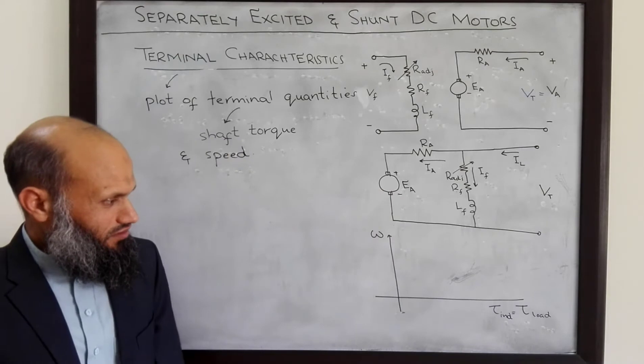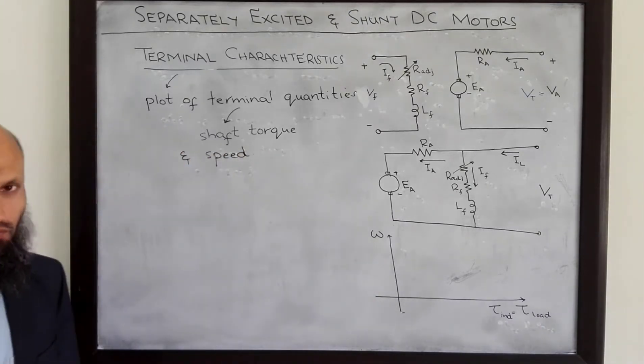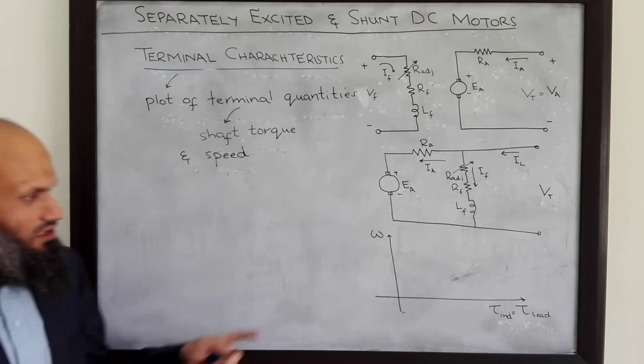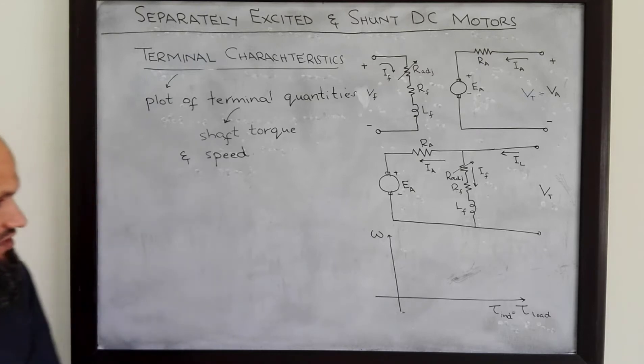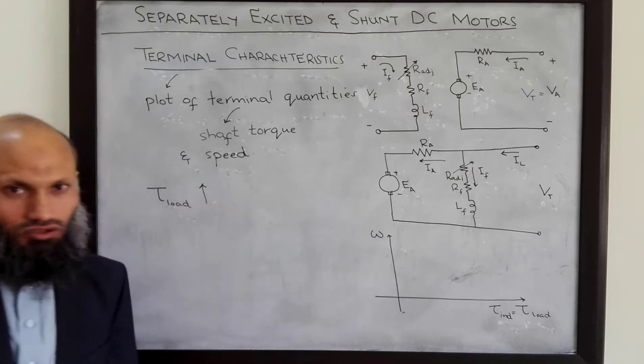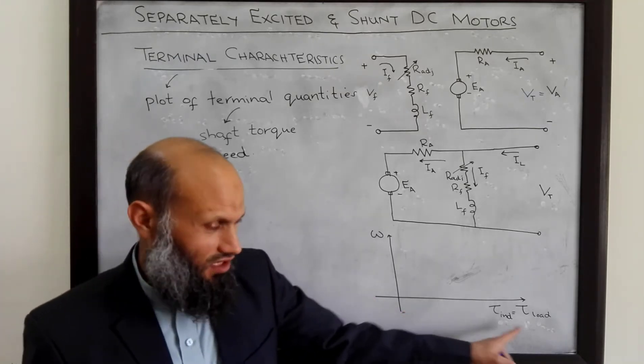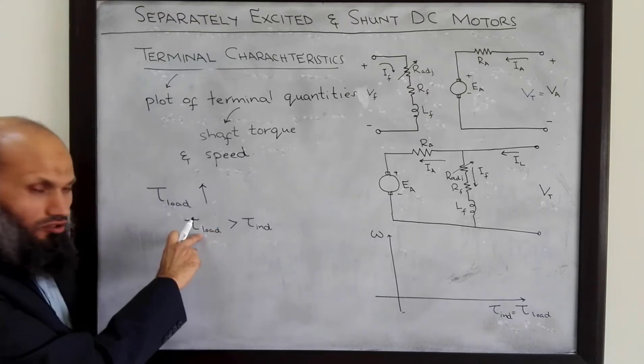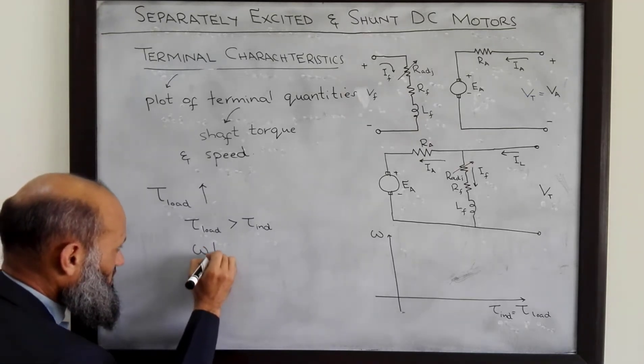At steady state, load torque and induced torque become equal. On the horizontal axis we have induced torque, which at steady state equals load torque, and on the vertical axis we have the speed of rotation of the rotor. First we shall discuss these characteristics intuitively. When we increase the load torque connected to the motor, during the transient the load torque will exceed the induced torque, and that will result in a decrease in the speed of the motor.